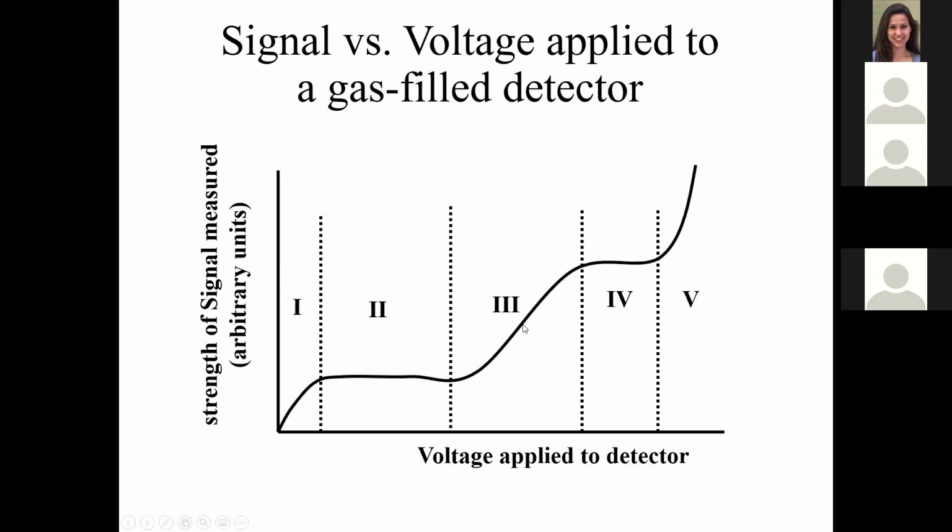So as you ramp that up, more and more of those secondary ionizations are going to occur, up to this region here, in which a single ionization event will avalanche into ionizing the entire chamber, okay? And so what that lets you do is, every time you get current through your system, that's a full ionization of your chamber, all right? And typically we're going to be measuring things either here in this current mode or out here in region 4 with our survey and dose meters.